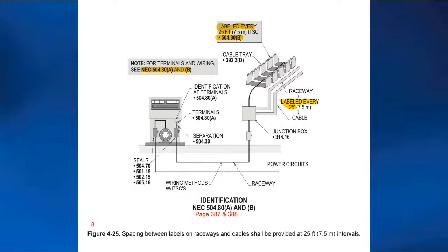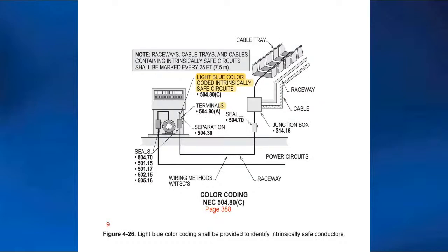Then, of course, color coding - where you terminate and everything, you color code those conductors light blue. However, I've seen in the industry where instead of putting a label every 25 feet on previous installations, they just sprayed it light blue for about 12 inches to identify it that way. But to me, the code says you need a label on the raceway or the cable, but you can put the light blue inside where you terminate. That's page 388, 504.80C.